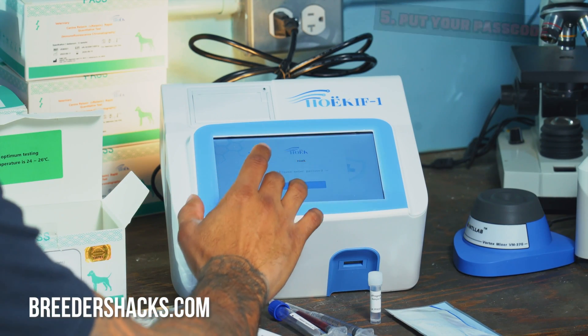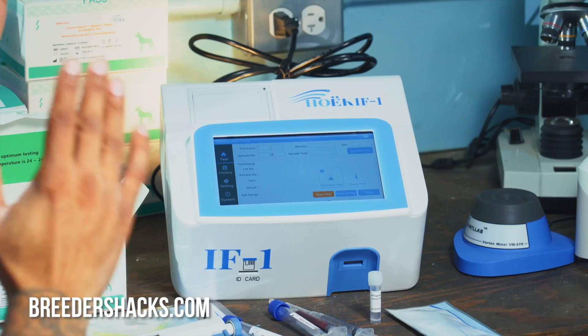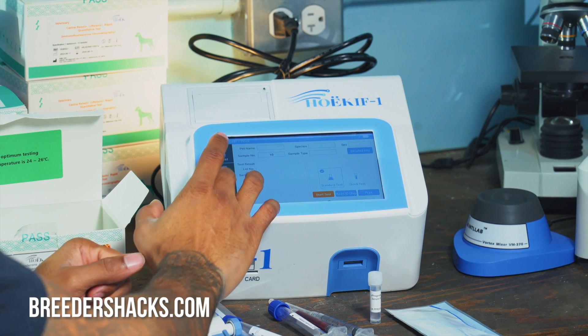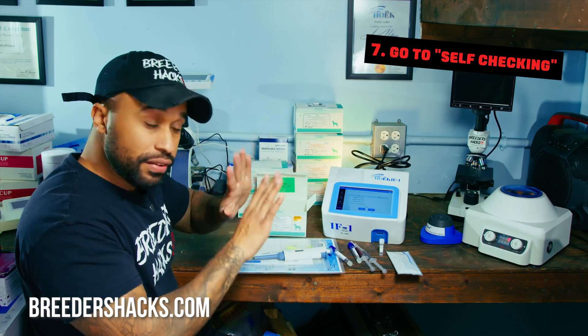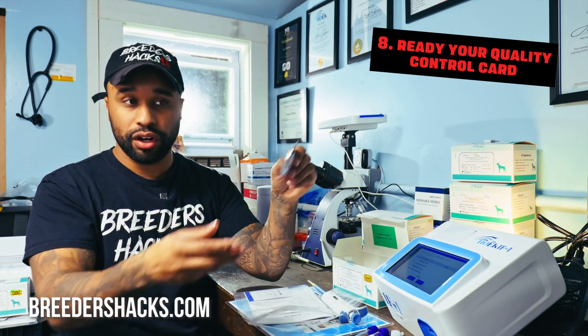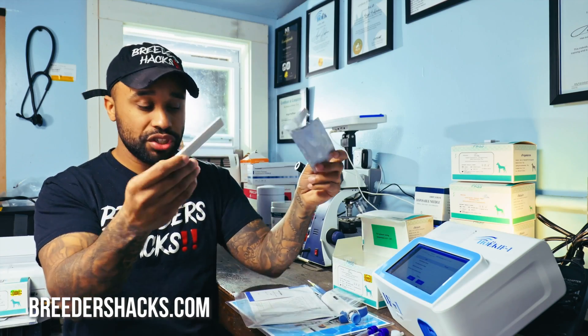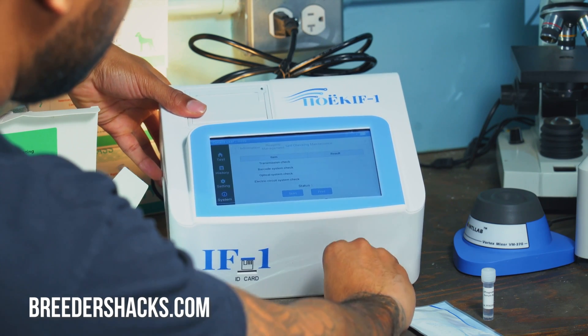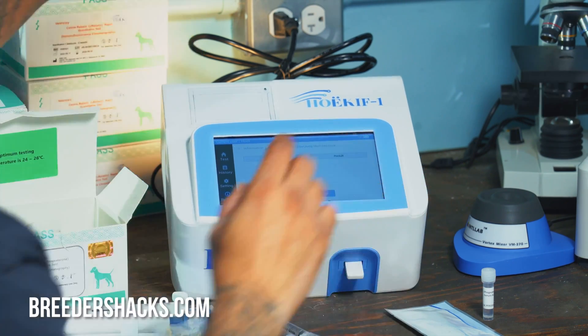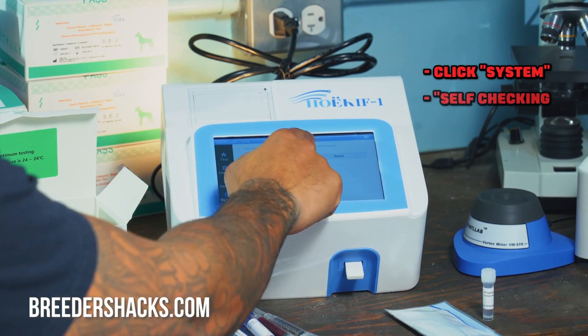Once the machine is powered up, put in your passcode — for me it's 1-2-3-4-5-6; every machine has its own unique password. Once you sign in, go to 'System,' click on 'System,' and go to 'Self-Checking.' Before we start running this machine and doing any tests, we want to make sure it's running accurately. We're going to take our quality control card — make sure you do not lose this; keep it with your paperwork.